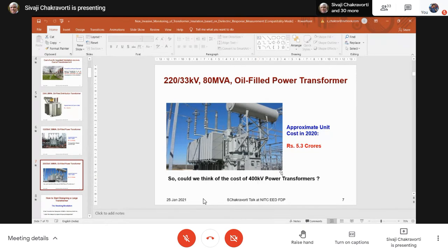So we have to be extremely careful in designing, isn't it? Because unless I design properly, then this 8 crore or 10 crore, when you put it on the line, the surges will appear in the line. Surges you cannot control, lightning you cannot control. And if I cannot linearize the potential, this 8 crore will burn and only white smoke will come out.